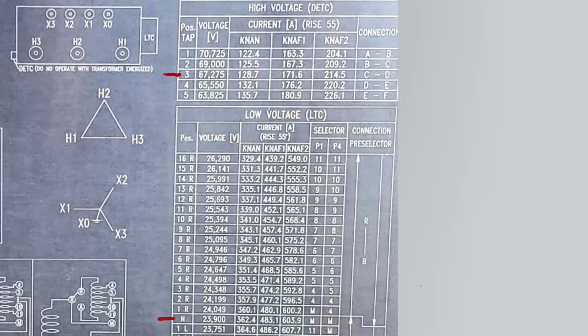So now that we have that, what is going? Look, there's probably part of this nameplate that I'm not showing, but we could calculate it if it's not there. So we have a delta on the primary and a Y on the secondary. This right here, if you look at this, this is going to be a DYN1, okay?